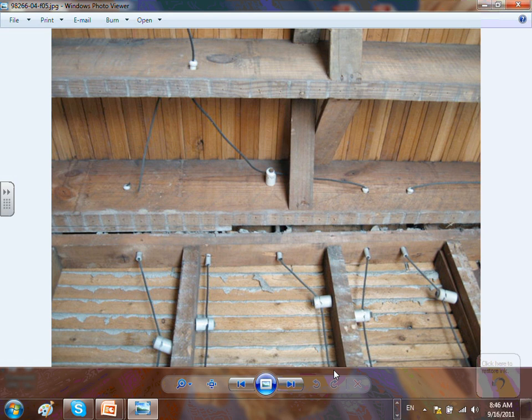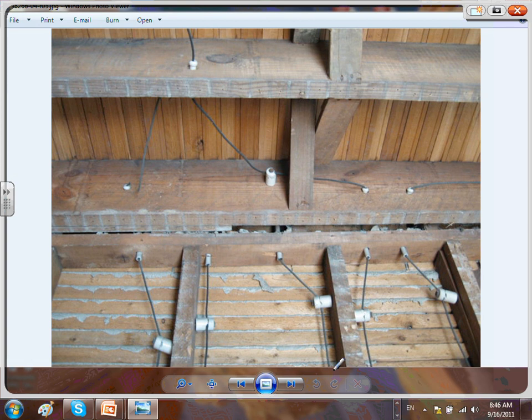Knob and tube — this is found in old houses. As designers, you will never specify knob and tube. But if you enter a building that has knob and tube and you want to tap into it, your obligation is to bring the knob and tube to a box, bring your Romex cable, and go from there. If the walls are open, you're supposed to remove it and do rewiring. If the walls are not open, you can put a J-box and tap from that J-box.